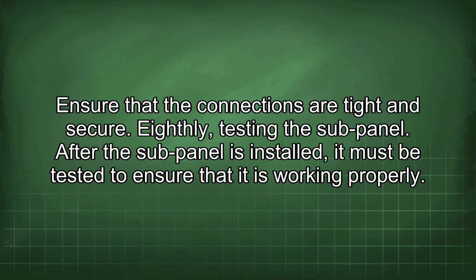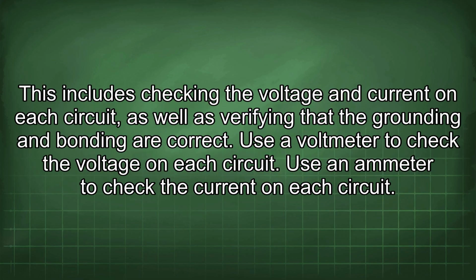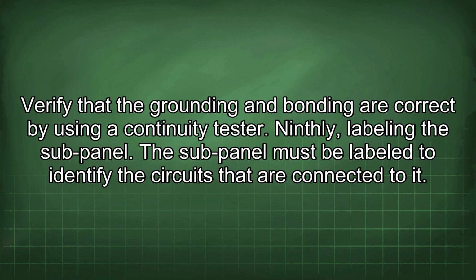Eighthly, testing the sub-panel. After the sub-panel is installed, it must be tested to ensure that it is working properly. This includes checking the voltage and current on each circuit, as well as verifying that the grounding and bonding are correct. Use a voltmeter to check the voltage on each circuit. Use an ammeter to check the current on each circuit. Verify that the grounding and bonding are correct by using a continuity tester. Ninthly, labeling the sub-panel.